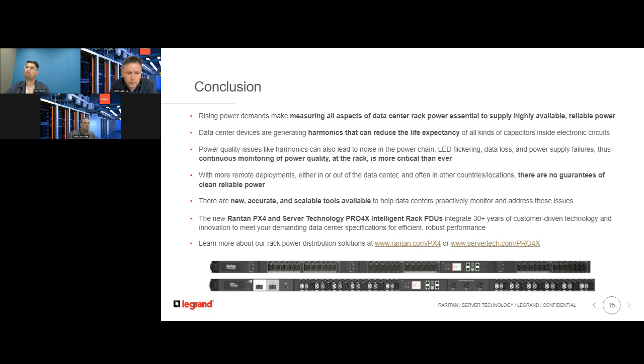Yeah. So for very accurate energy metering applications, it's extremely important that the PDU can constantly measure current and voltage and precisely calculate the power and the energy based on this data. But the PDU should also be able to buffer the results of this calculation over a certain time period. Our network controller is able to buffer this data for a certain amount of time, which allows a DCIM system to receive a chunk of measured data at once. So you're not losing metering accuracy if you only poll the PDU after, let's say, 1 minute or so. And this is possible. You don't have to constantly stream all the measured data into a DCIM system, because the PDU is able to buffer the data.